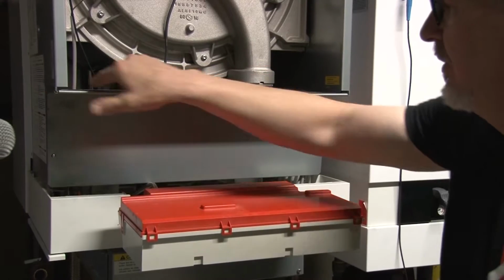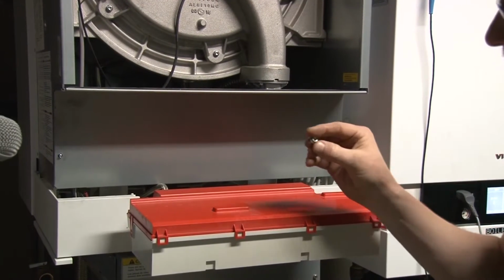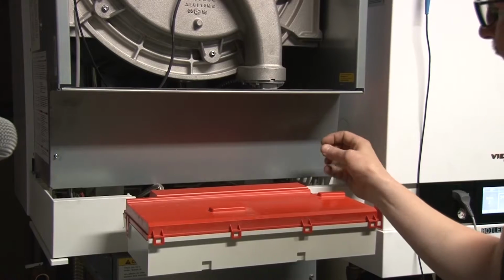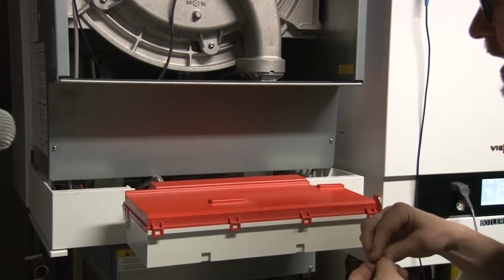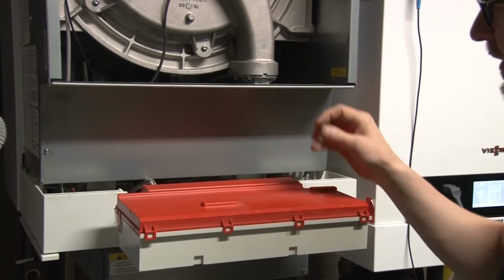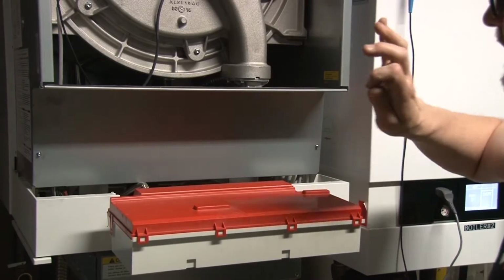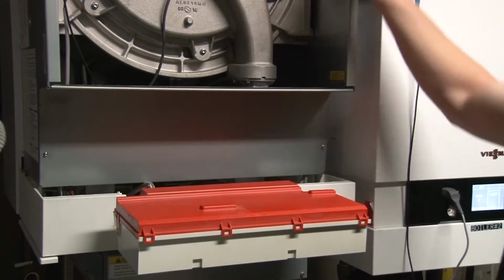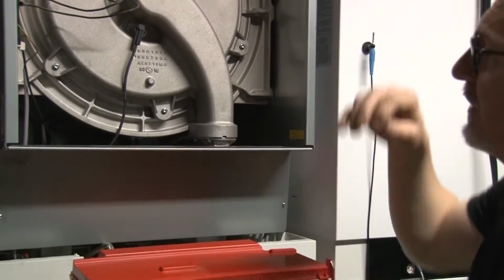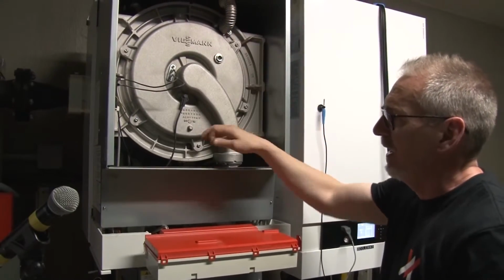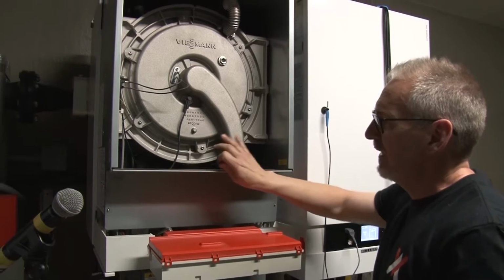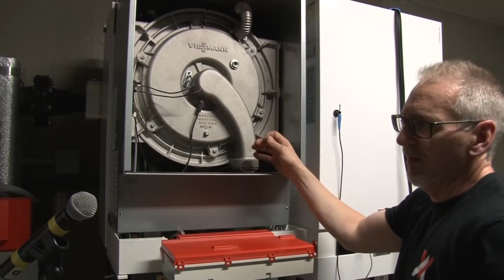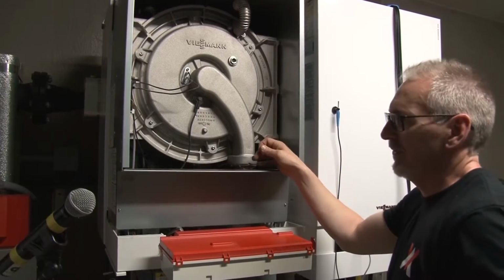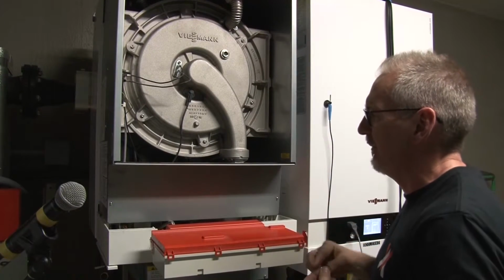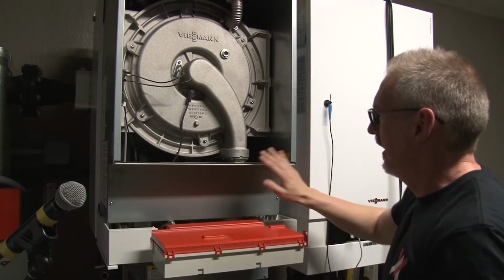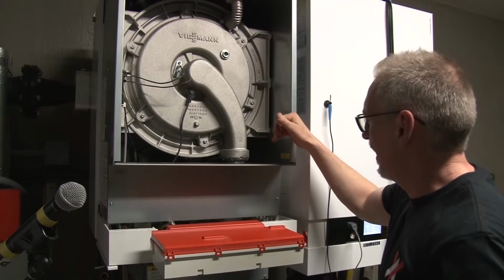to service these boilers. So once I get to this point, I've got these little 8mm nuts. You're going to back these off. I loosened them up here already, but we would tighten these back. And they're just basically holding this enclosure in. When I put that door back on, it seals this whole area. That means that if I've got a 2-pipe system, so I'm pulling combustion air into the boiler, with that door on, it's completely sealing, so we're not stealing air from the room. We're taking all our air from the outside. So it just depends on how you have that combustion air piped as to how important this little angle bracket is as far as its operational function.